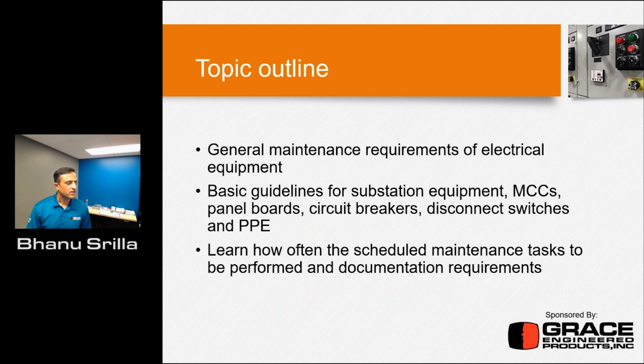So the topic outlined for today is general maintenance requirements of electrical equipment as it applies to NFPA 70E, and the basic guidelines for substation equipment, MCCs, panel boards, circuit breakers, disconnect switches, and also the PPE. This is more in alignment with what Chapter 2, which is Article 200, talks about in NFPA 70E, and also learn how often the scheduled maintenance has to be performed on those equipment as well.